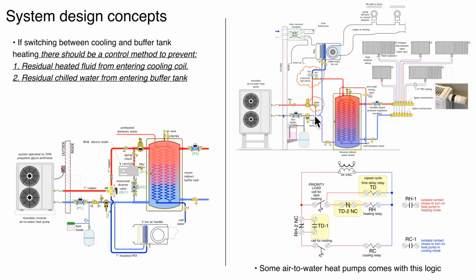So it's going to change its temperature quickly. If it was 120 degree fluid and the heat pump comes back on in cooling, literally probably in less than a minute, it's going to have that fluid down to a temperature at which you can then open this valve and allow that chilled fluid to go up through the coil and not create that slug of hot air that you would get if you simply switch with a 3-way valve.